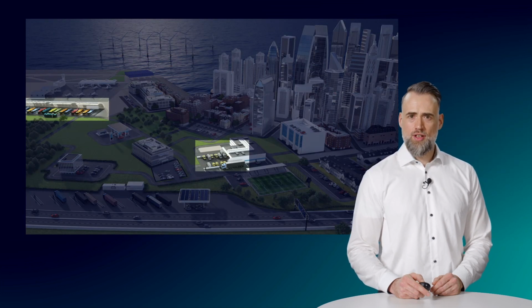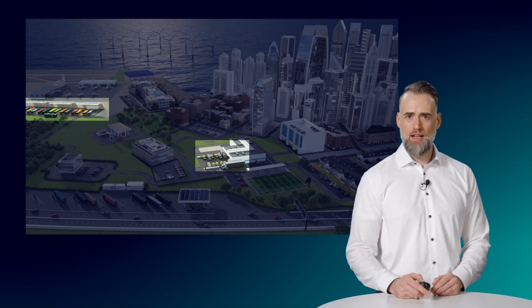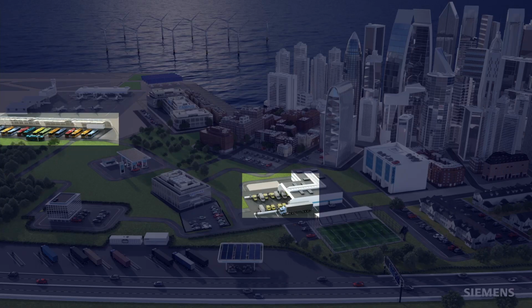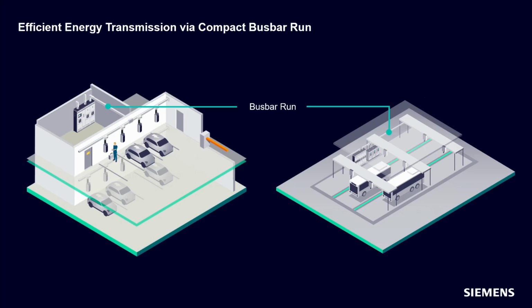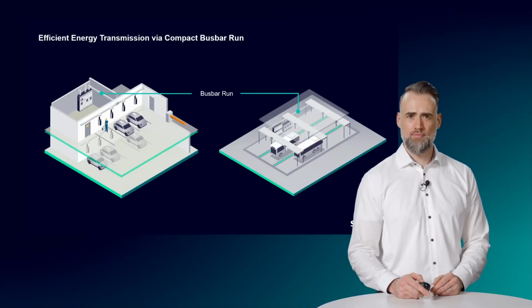For higher charging capacities, such as those required for e-bus or e-truck charging stations, our LD and LI high current busbar trunking systems are ideally suited. Both the energy transport from the transformer to the low voltage main distribution board and the supply of the individual charging stations are carried out via a compact busbar run.